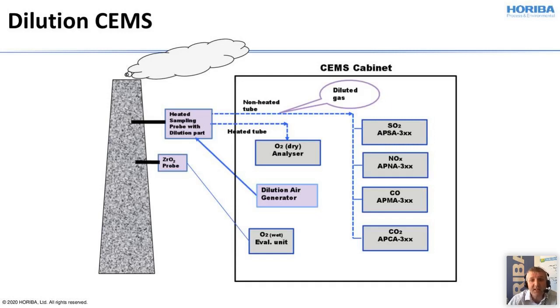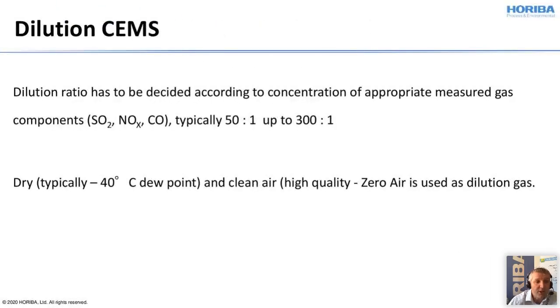Another disadvantage in this case is that the sample gas is already diluted, and we don't know the humidity level anymore. So with a zirconia oxygen probe, for example, we can analyze the wet oxygen, and from the difference between the wet oxygen and the dry oxygen we can calculate the humidity level of the sample gas, so that we finally correct all the measured values to a dry gas basis. The dilution ratio, which has to be decided according to the concentration of the measured gases, is typically between 50 to 1 and 300 to 1, depending on the concentrations.